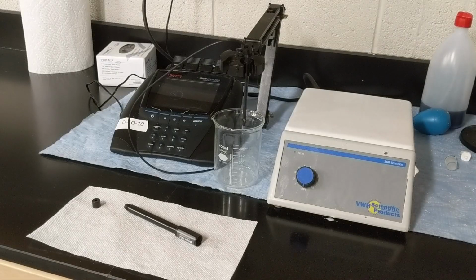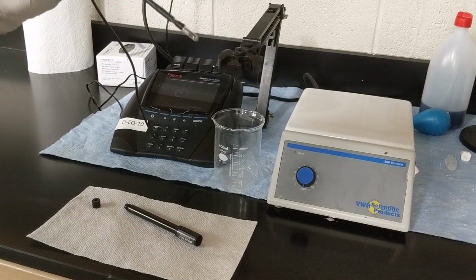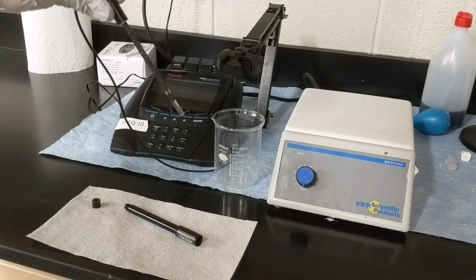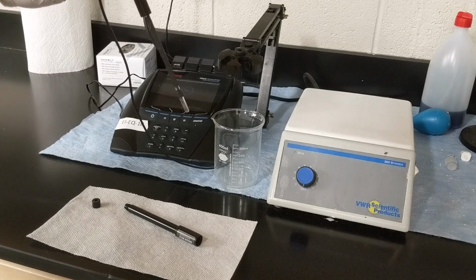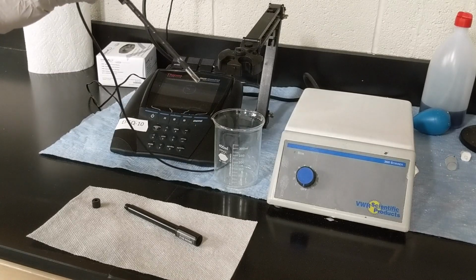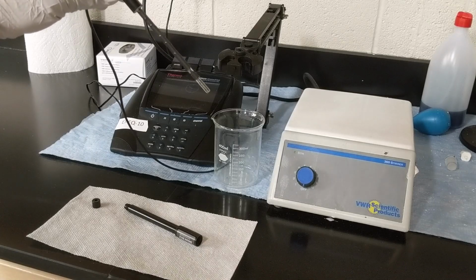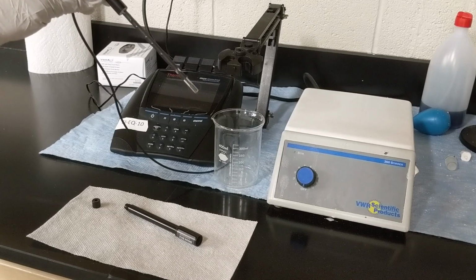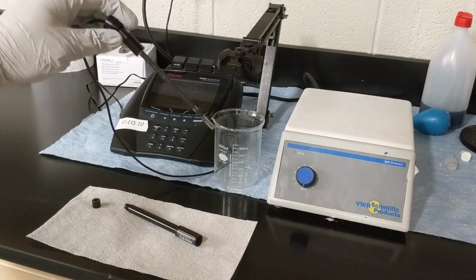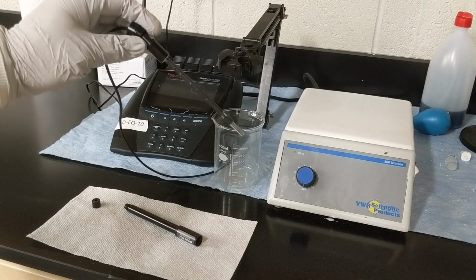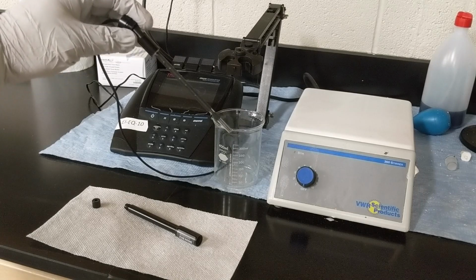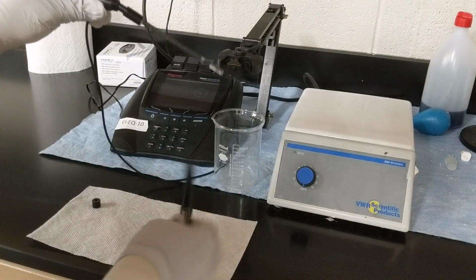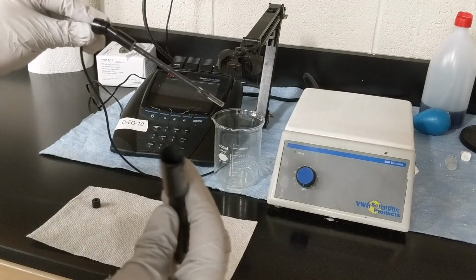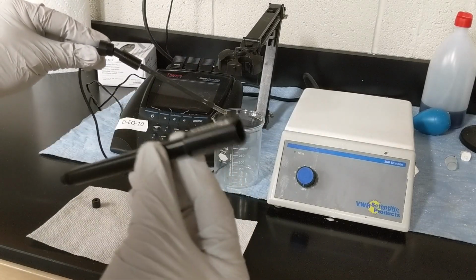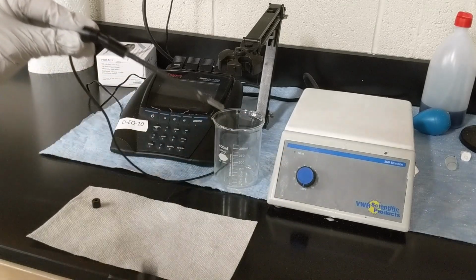Here is our setup for the ammonia meter. What you may notice at first is that this electrode is actually just sitting out dry, and that's maybe the first thing that differentiates it from our pH electrodes, where those are all a self-contained unit that needs to be kept in its storage solution at all times. This, if we're not going to use it for long extended periods of time, we will take the whole thing apart and let it dry out. Down here is actually the outer casing, and when we put this together, we're going to have the filling solution in the outer casing surrounding this inner electrode.